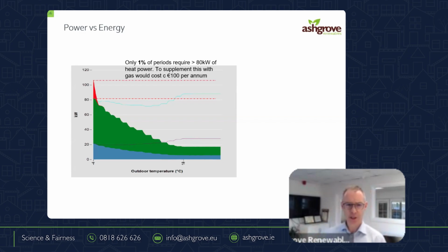So the heat pump will continue running, but importantly, I suppose, if that gas boiler or oil boiler gets pulled in, the heat pump has to control it. Otherwise, what you don't definitely want, and we've seen it over the years, the gas boiler kicks in, all of a sudden it starts to take control. It's producing hotter temperatures or higher temperatures, and all of a sudden the heat pump stops because it looks like it's no longer needed, and now off goes the heat pump until somebody tells it shouldn't be running. So we would encourage, when you go up into the larger systems, that I'm not saying you always undersize.